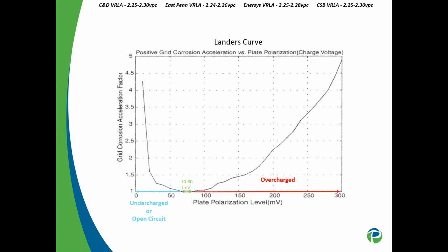You can see the small window on the bottom. They actually measure from the separator to the positive post, and they're looking for that plate polarization level. When they're designing or specifying the float spec for their battery, they look at those values. As batteries start to get overcharged, you can see this is your corrosion rate. Way overcharged, you're getting a high level of corrosion. Way undercharged or open circuit, you're still going to get a high level of corrosion. This is the sweet spot, and the float spec reflects that sweet spot. If they stay in that range, they minimize the corrosion rate of the batteries.